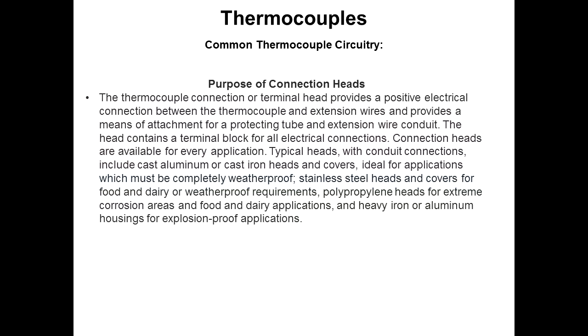The purpose of connection heads for thermocouple and RTD probes is to provide a place for the probe to screw into. The wires come out into a protected area. They're connected to a terminal block, either with a transmitter output from there or another connection for extension wire to run out to your end use.